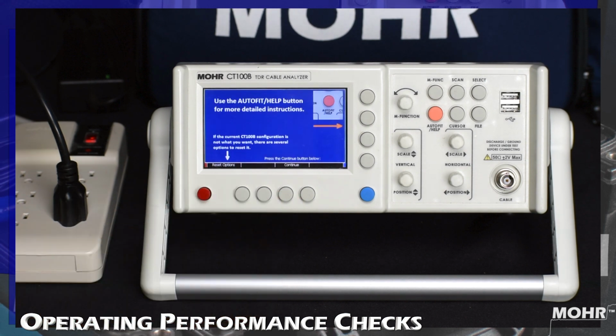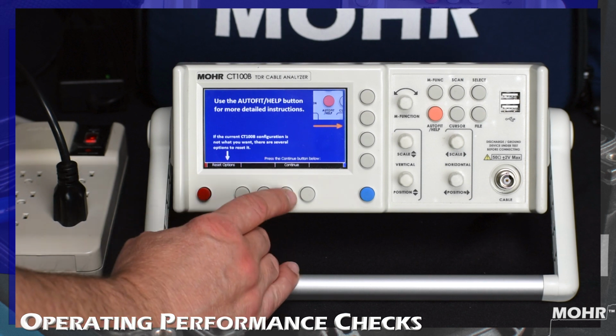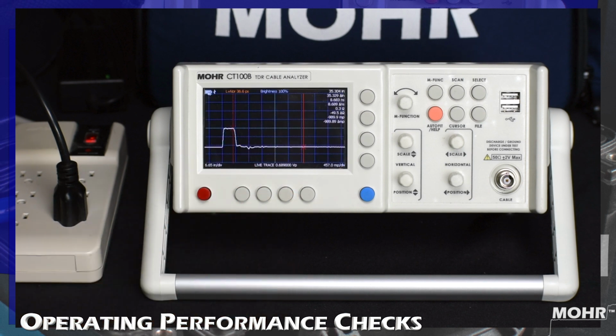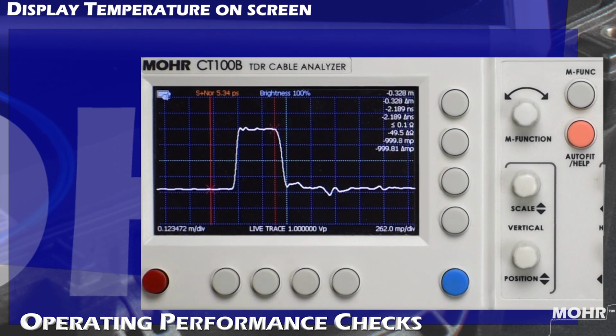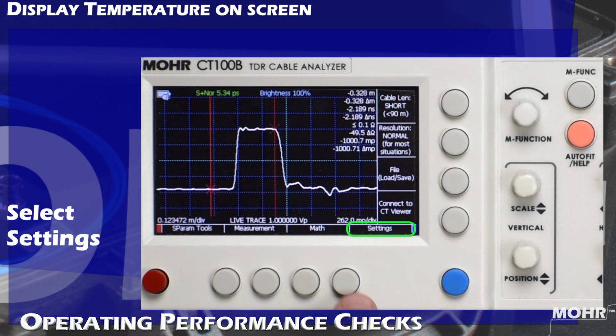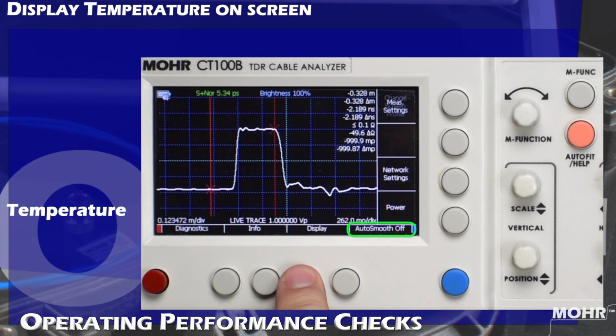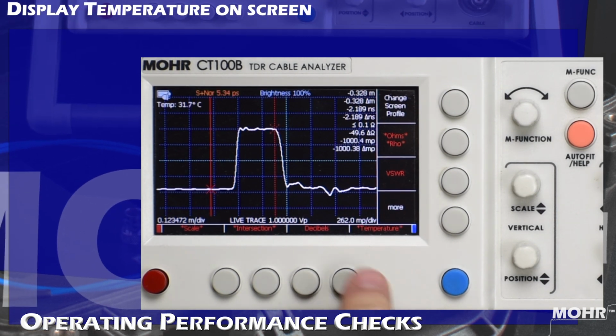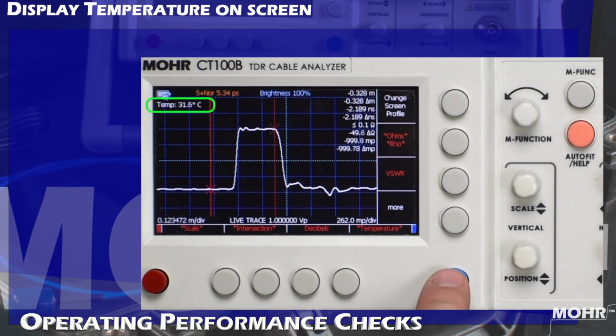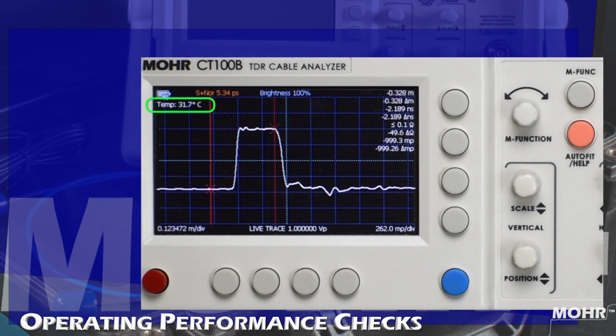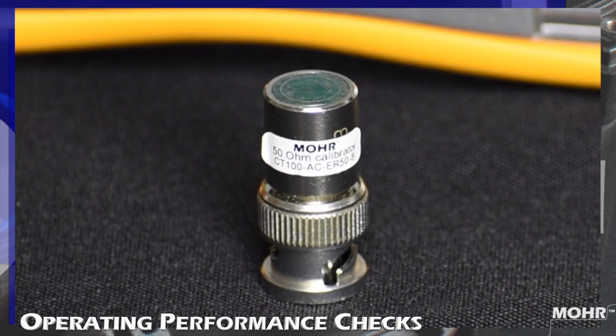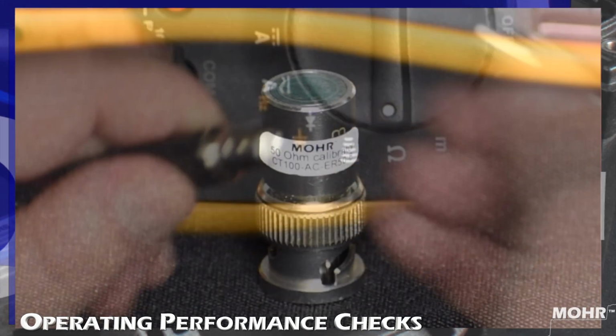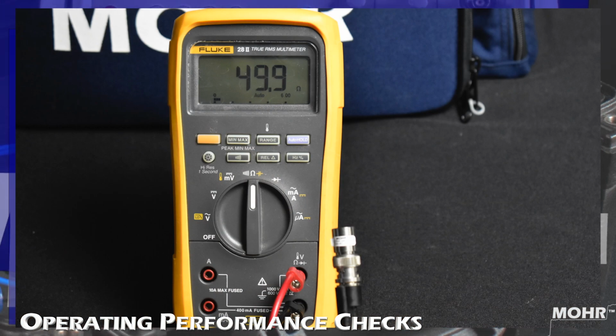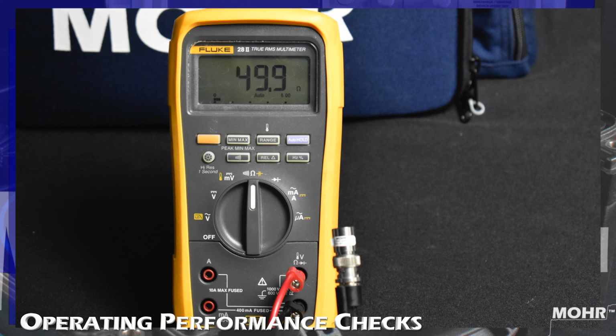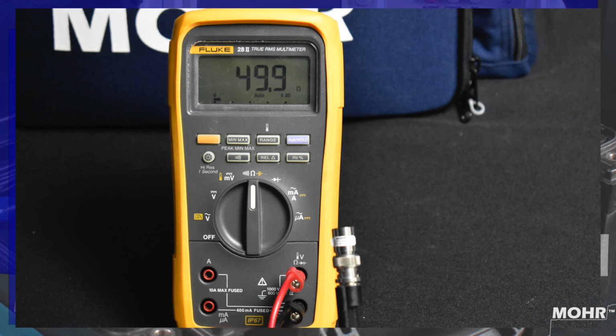Allow the unit to warm up till it displays a steady temperature. To display the temperature, press the menu button, select Settings, followed by Display, then Temperature. The temperature will display in the upper left corner of the screen, just under the battery icon. We need to verify our calibrated 50 ohm terminator by connecting our volt ohm meter, and we can see that this one is 49.9 ohms and well within tolerance.